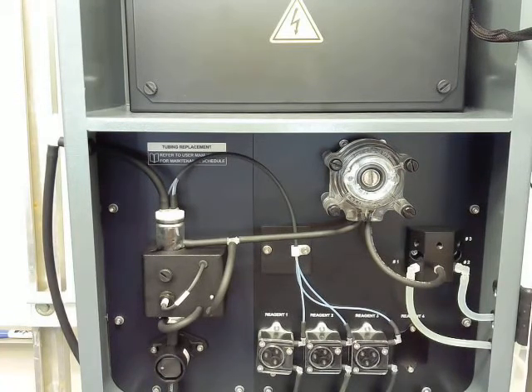So once we fill up the flow cell this time, we'll start adding our reagent. Again, this timing and the reagent timing, the mixing timing is all going to be a little different based on the chemistry of the copper, the monochloramine. Watch this focus here, we'll have our first reagent, similar to the copper. In the case of the monochloramine, both reagents actually get added at the same exact time. So you see both reagent 1 and reagent 2 being added.